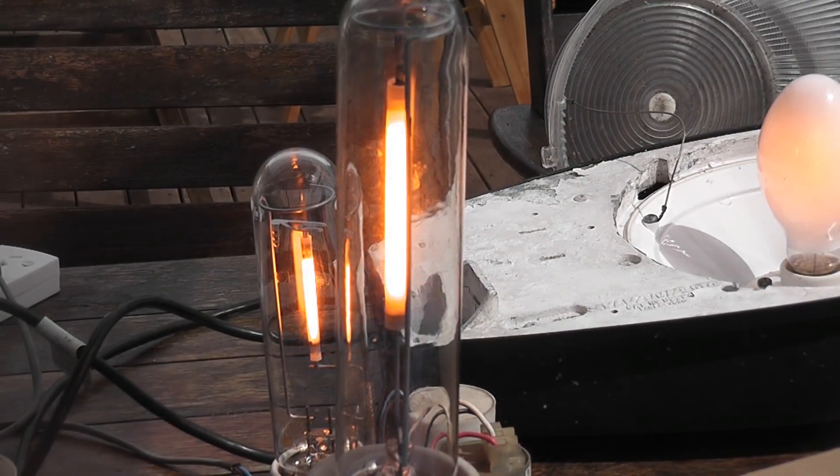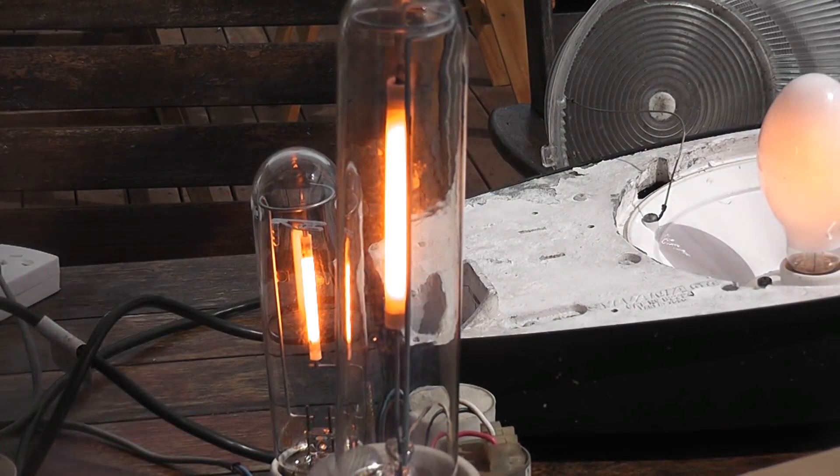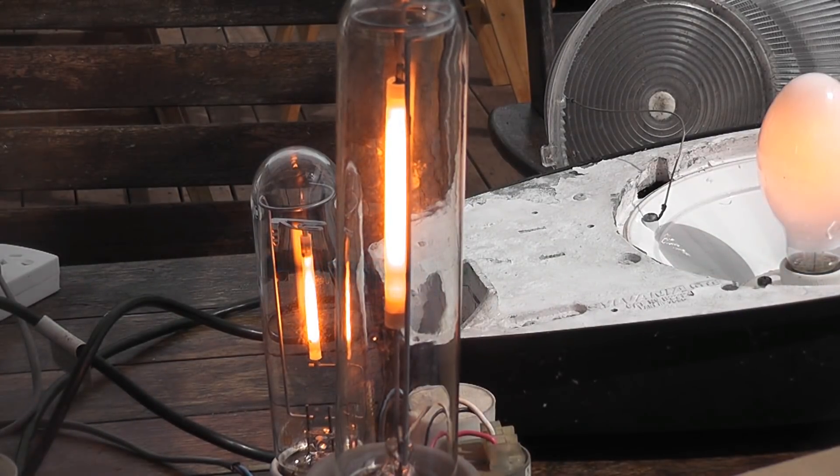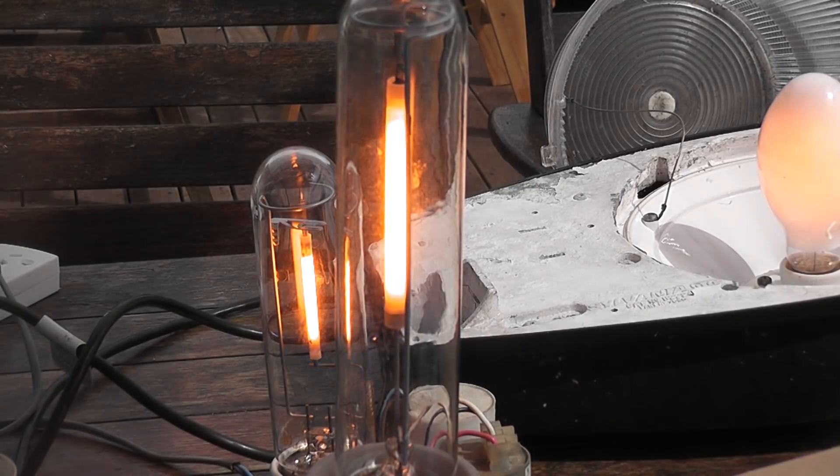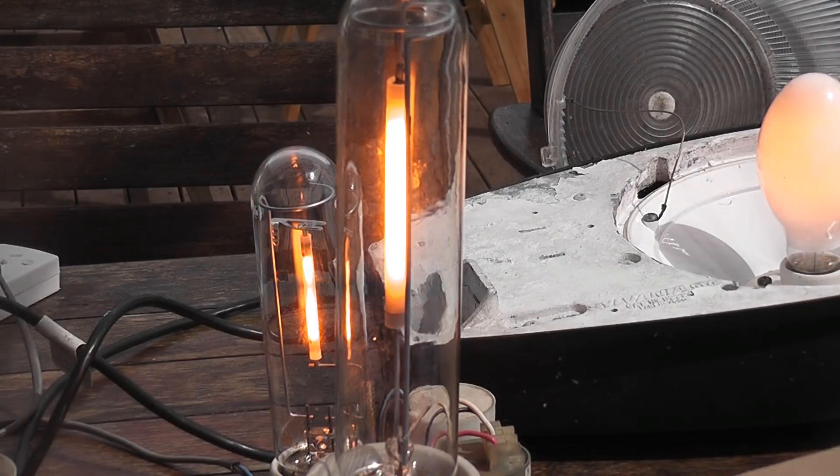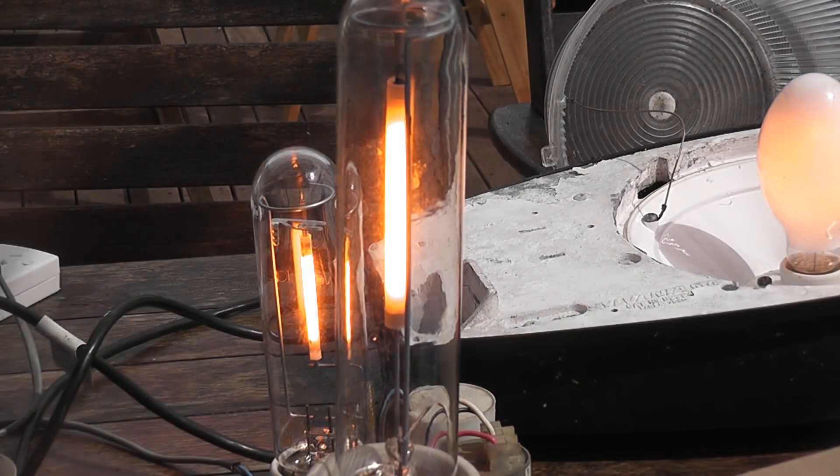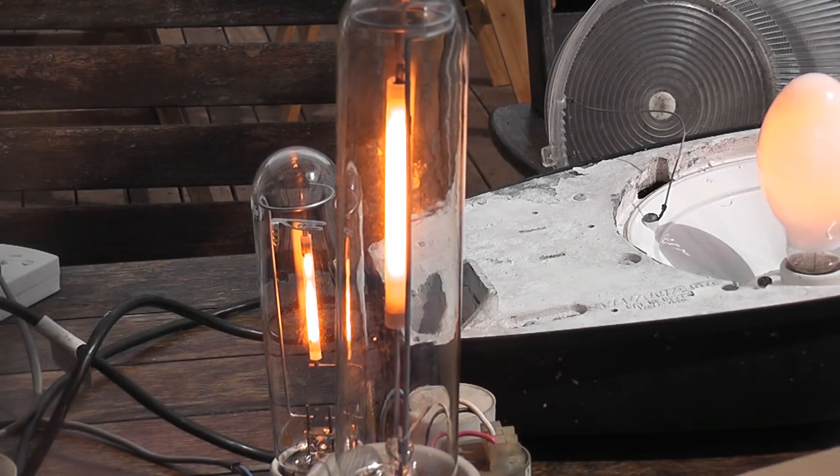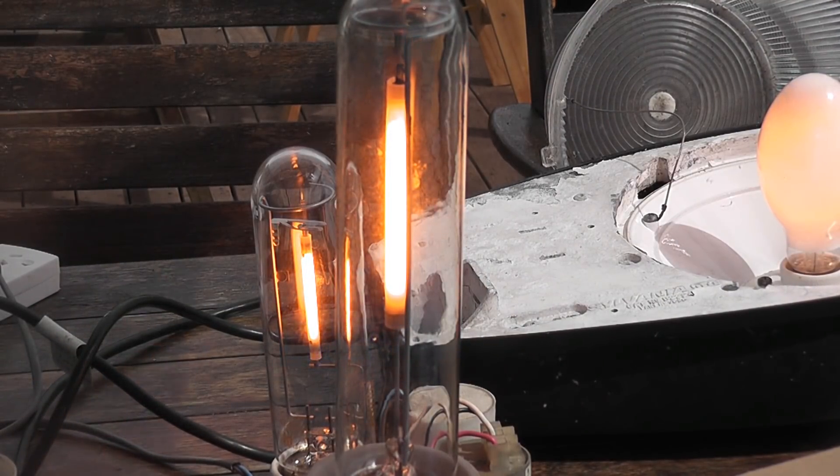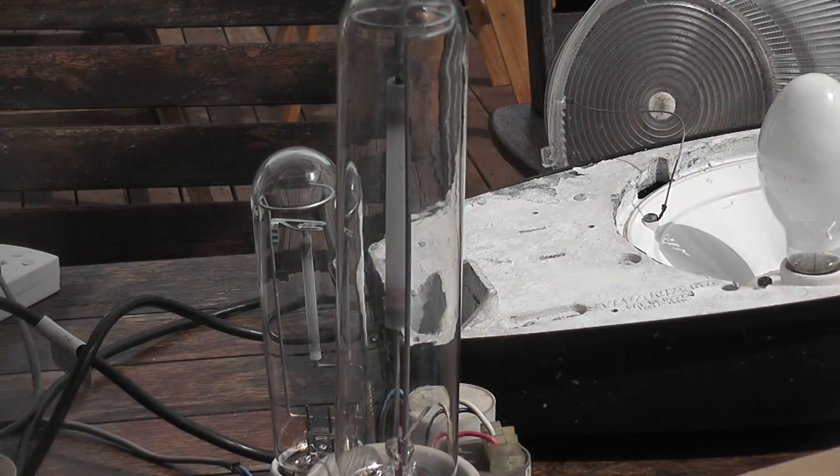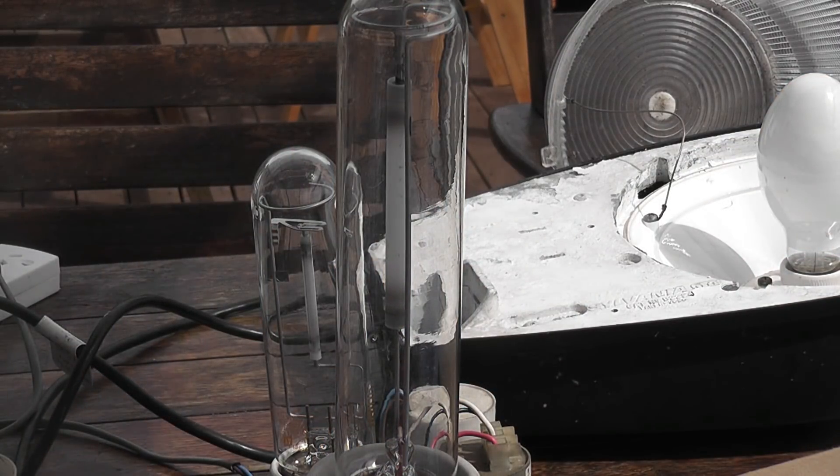And I'm going to take the cover back of the photo cell and let it switch off again. Photo cell opened up. Count down. Three, two, one. Switch off. Not yet. It will have a hysteresis cycle in there. We'll switch off shortly. Capsules have time to re-strike. It's normally the test mode when you swap a photo cell into a socket. The lights come on. There we go. The lights are off. De-energized capsules.